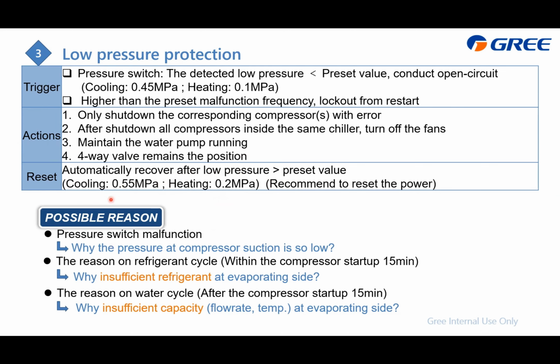So just focus on the possible reasons. The first is to check whether the pressure is really so low or not. And of course, after that, if the error occurs within 15 minutes of the compressor starting up, you need to focus on the refrigerant cycle, and ask why there's not enough refrigerant at the evaporating side. And after 15 minutes, just focus on the water cycle. Why is there not enough capacity? Maybe the water flow rate or the water temperature is not that good.